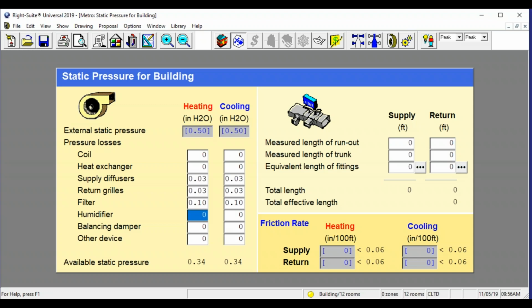All right, now typically your available static pressure should be between 0.3 and 0.4 by the time that you do your pressure losses. I've seen a lot of times where people put the coil in there, but if you go through and you read your manual D and you read a lot of the different literature, your coil is often included in there. It's the same thing when you do your heat load calculation.